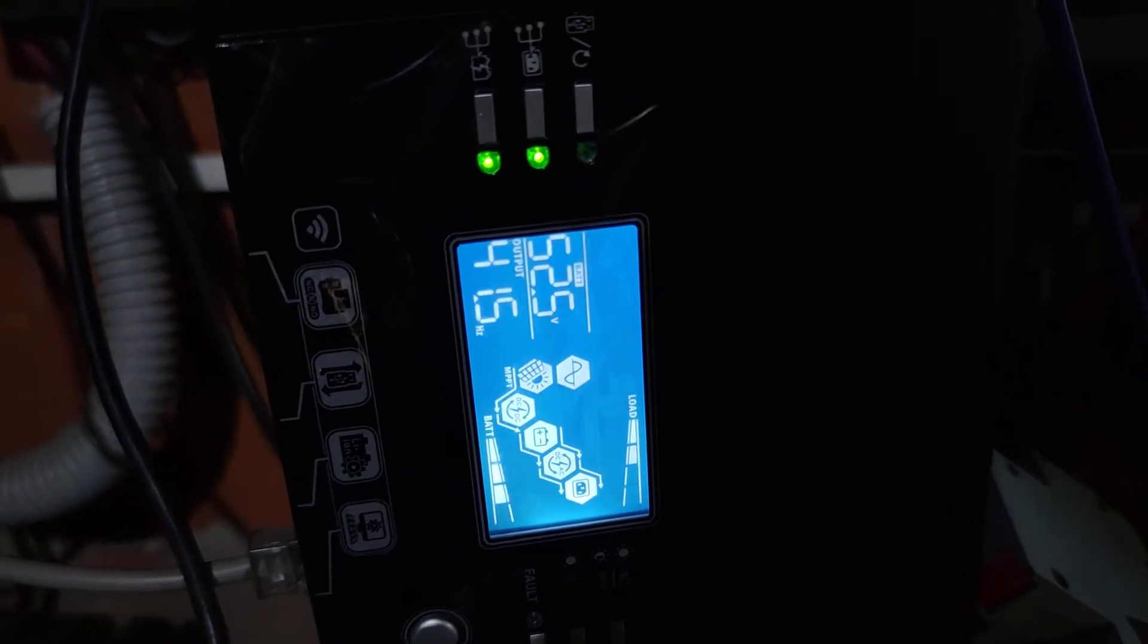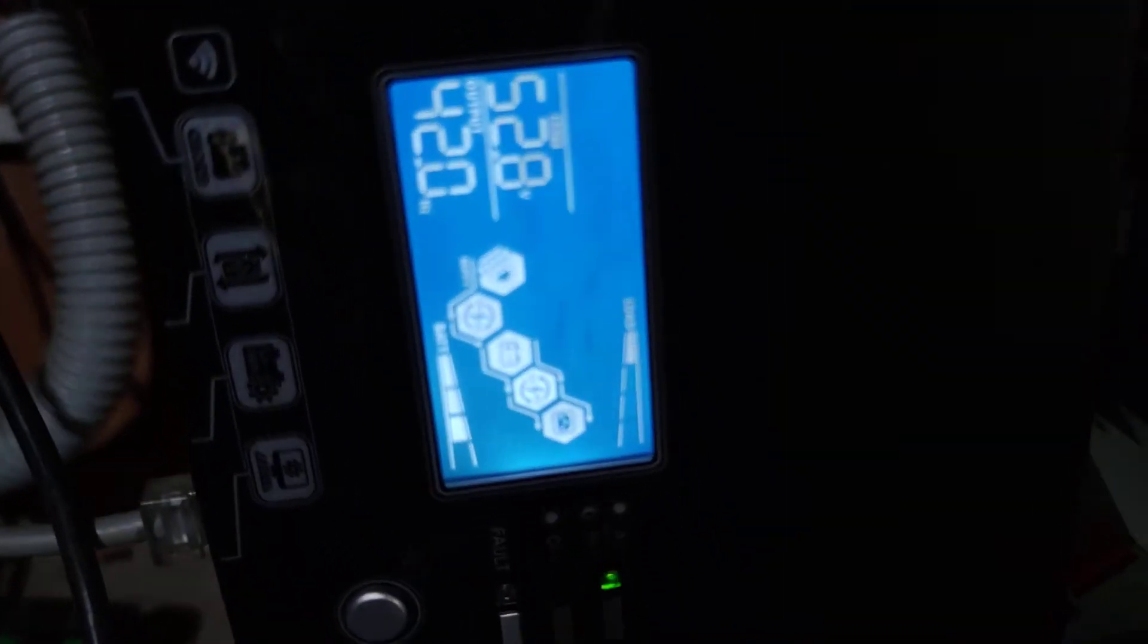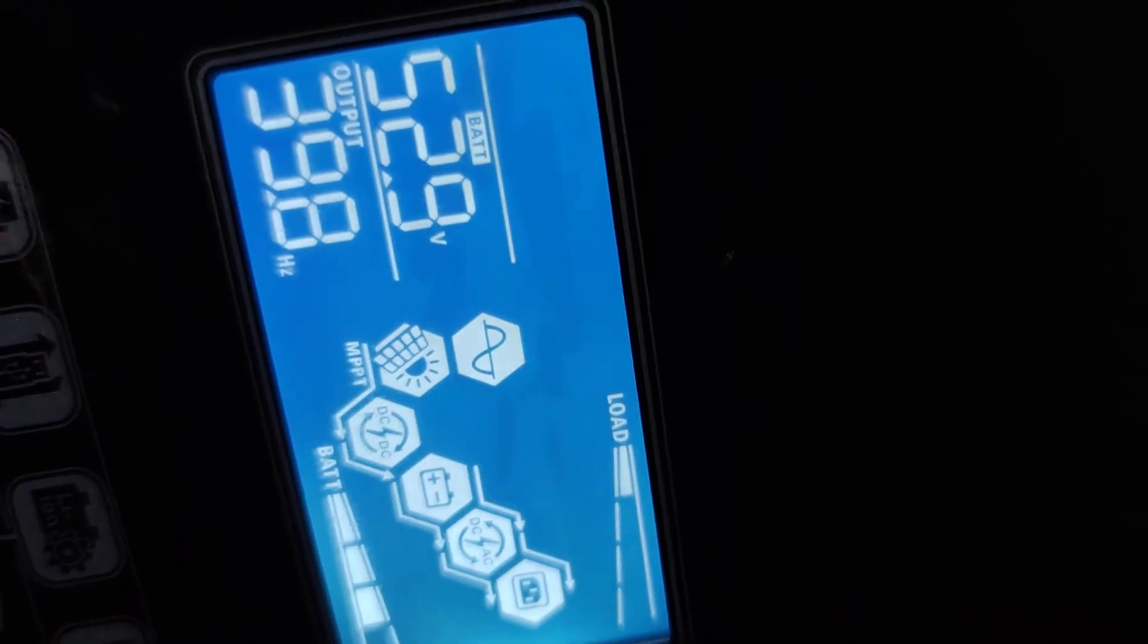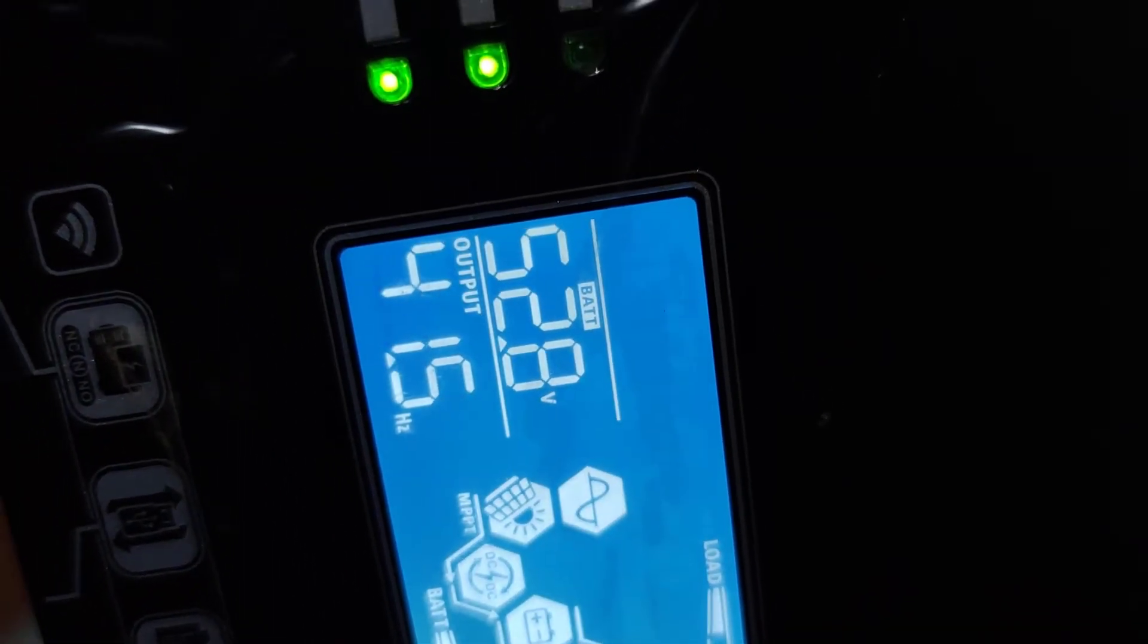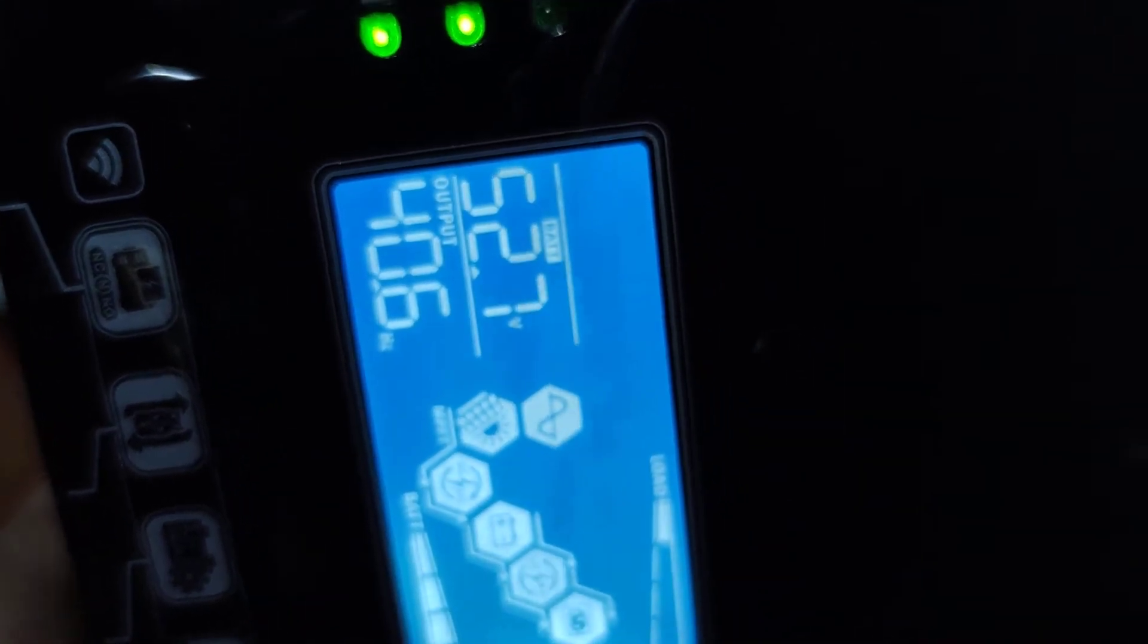If I were to connect the line wire now, it would have the same impact as previously. And look what happens. It detects the input, check out the blinking phase wire. And look at the output Hertz. Output Hertz is constantly on 41, 40. Correcting, I guess this is the minimum at which it tries to correct itself and then not going below that.